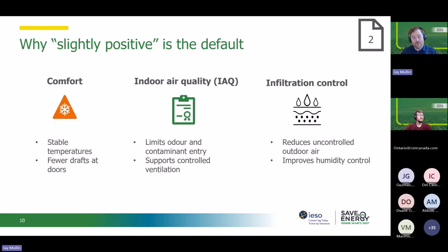For industrial facilities that don't have specific requirements around positive or negative pressure, it's often recommended to keep them slightly positive. This can help improve comfort because it helps keep temperatures more stable, because you're pushing air out, but that's conditioned air. You're not drawing in cold air through drafts in the winter, so it improves comfort. It can improve indoor air quality because it limits odor and contaminant entry into the general space where people are working, helps better control ventilation, and it also helps with infiltration control. So keeping uncontrolled outdoor air from coming into the facility in the summer, which can bring in a lot of humidity, can also impact comfort.